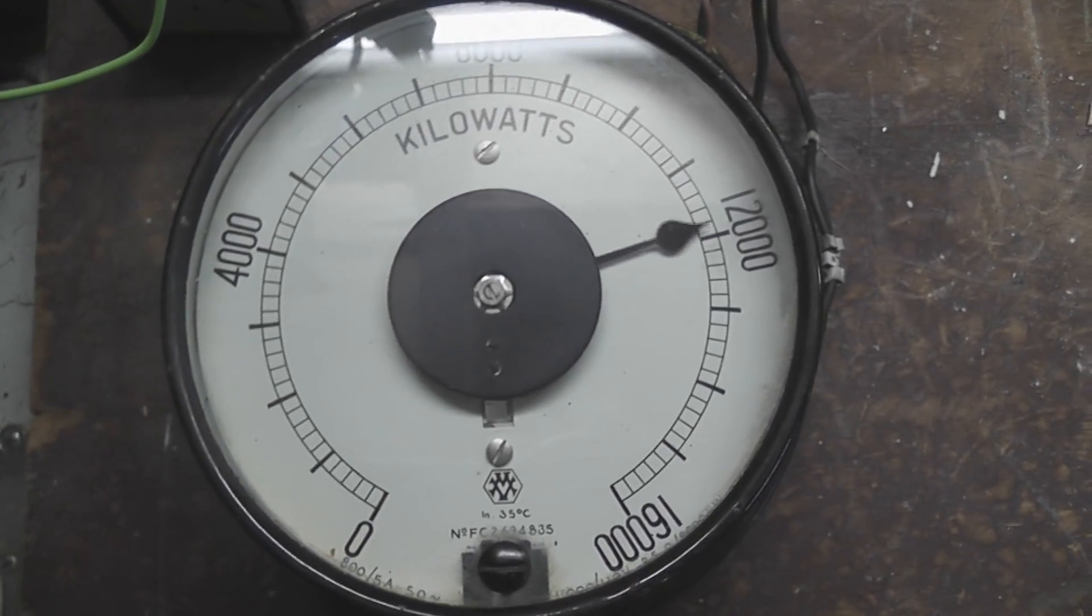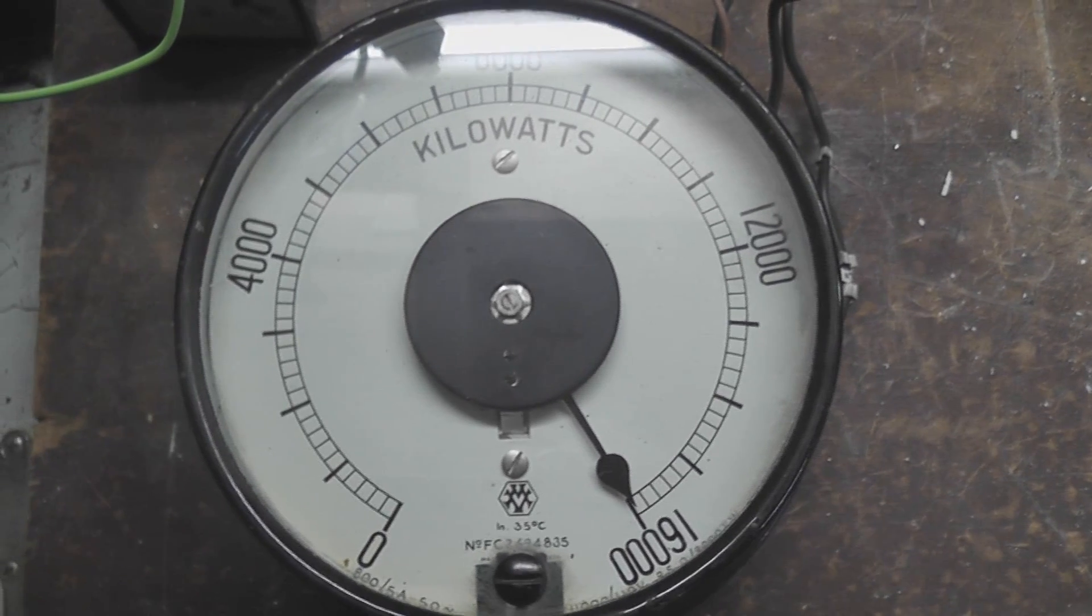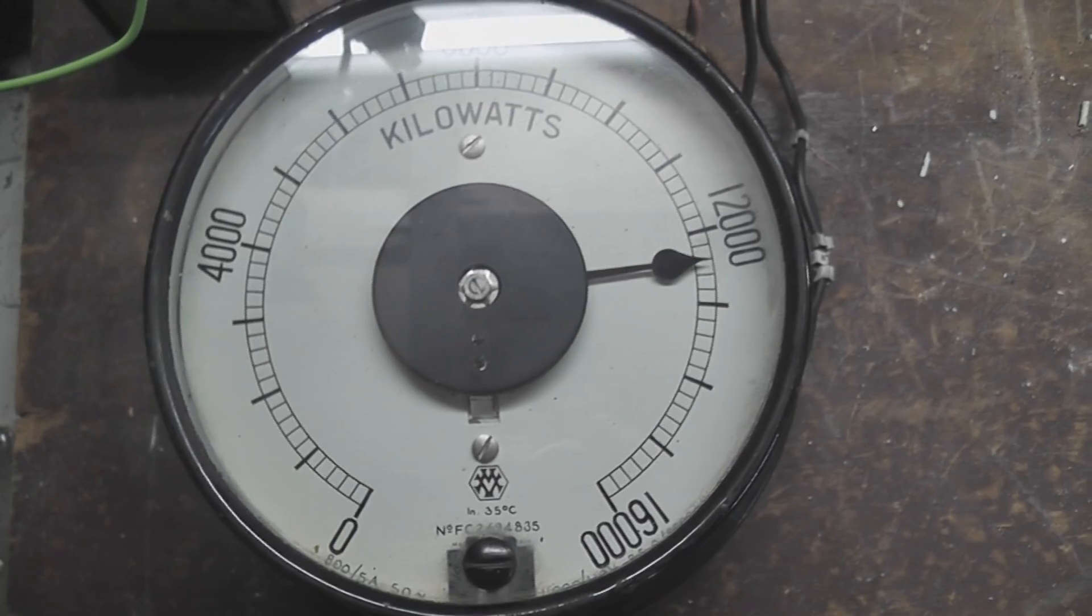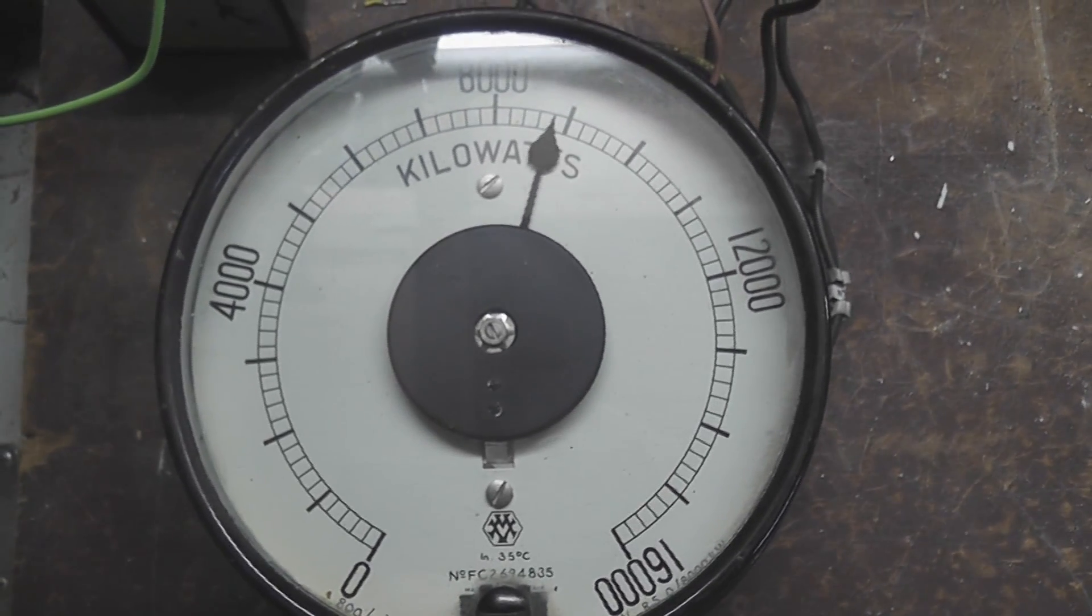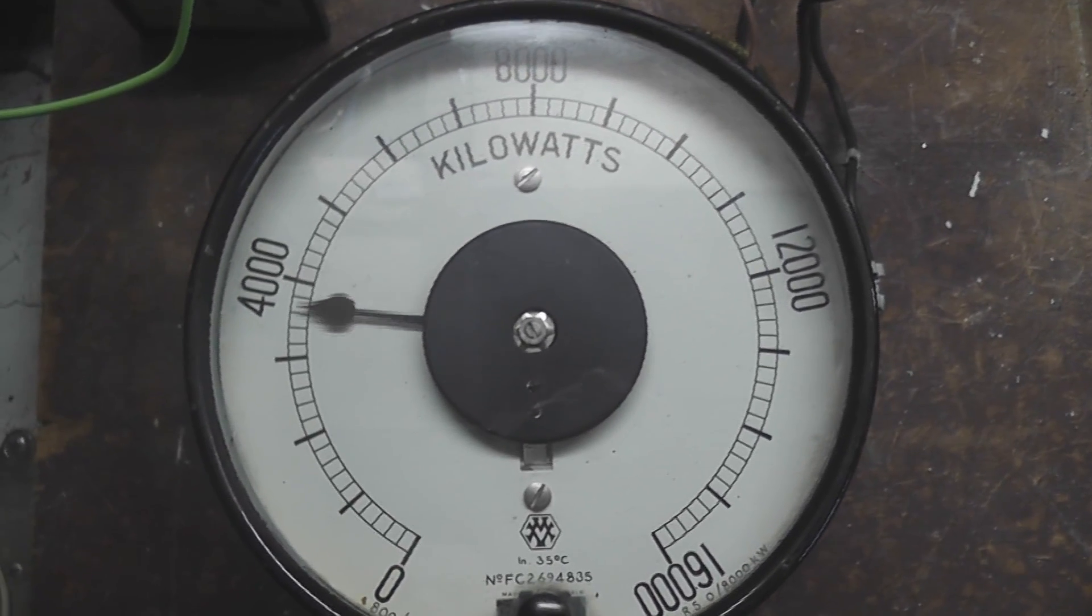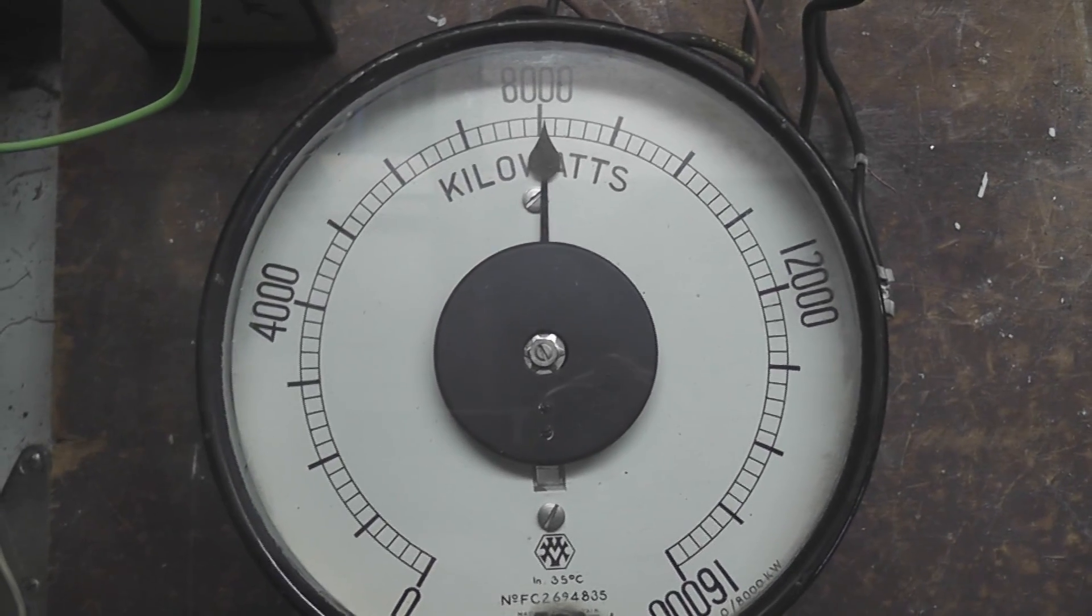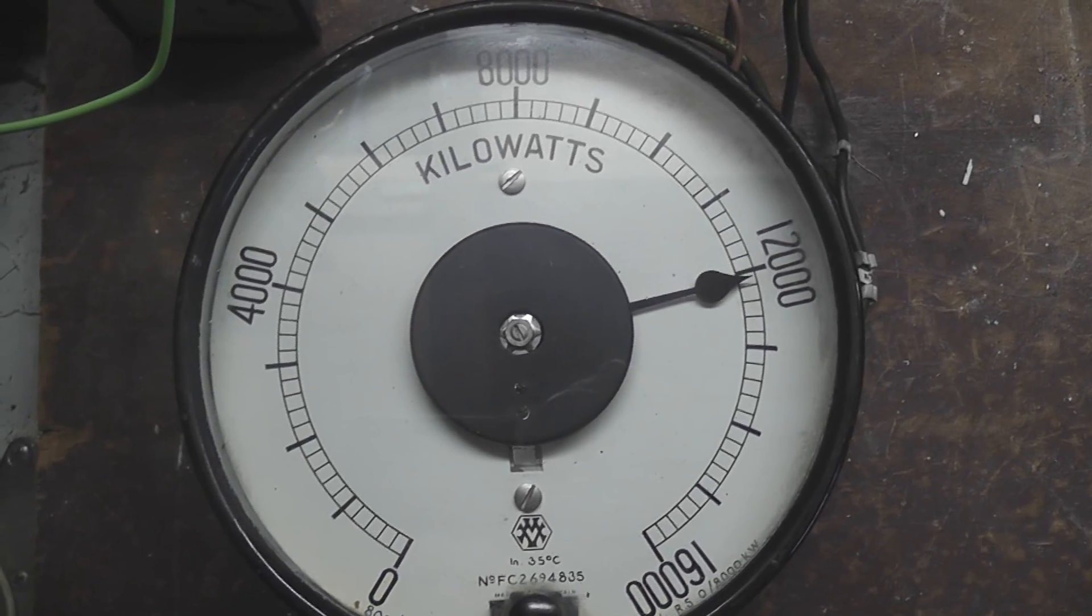I know it's a wattmeter with 110 volt potential coils. I'm just going to build it in one of my control boxes and calibrate it for kilowatts. Get a suitable ratio CT current transformer and get it to read like four thousand for four kilowatts, eight thousand for eight kilowatts and so on. That's the plan. I'll see what happens.